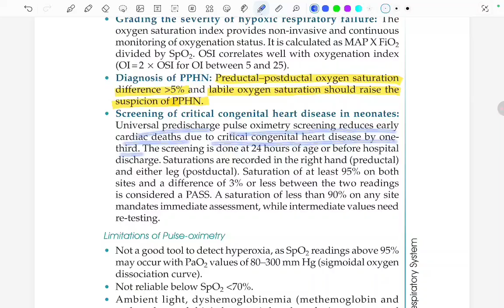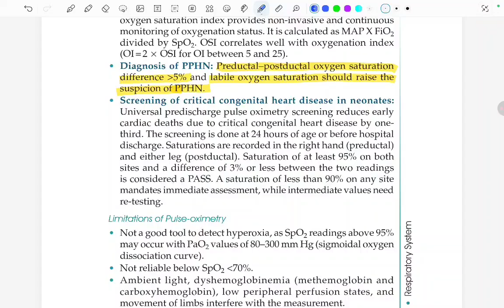The screening is done at 24 hours of age before hospital discharge. Saturations are recorded in the right hand, which is preductal, and either leg, that is postductal. Saturation of at least 95% on both sides and a difference of 3% or less between the two readings is considered as PASS. A saturation less than 90% on any side mandates immediate assessment, while intermediate values need retesting.